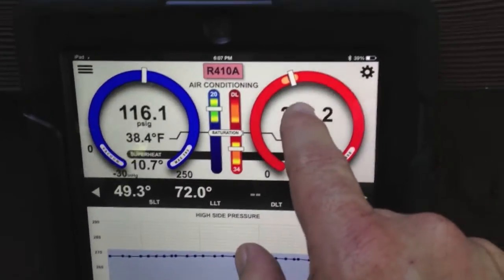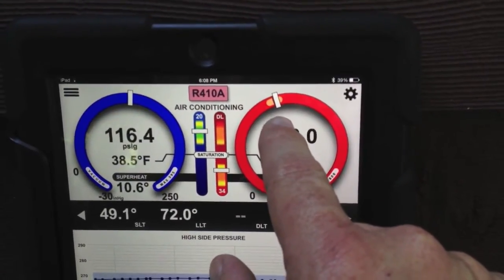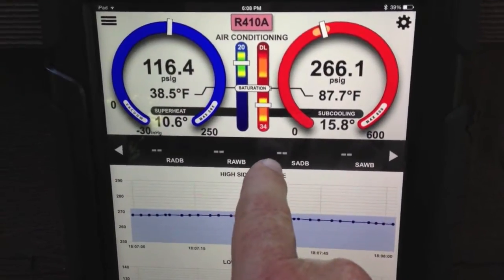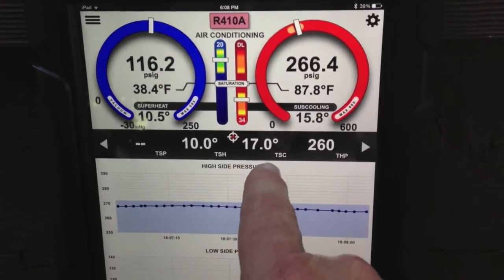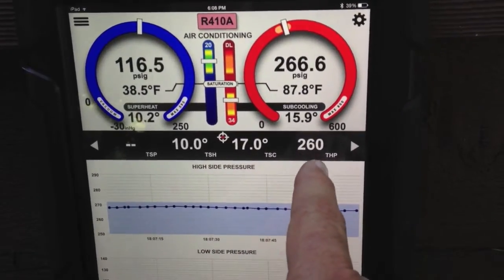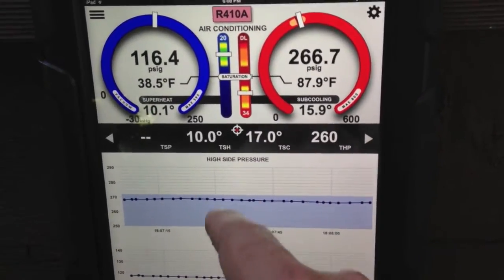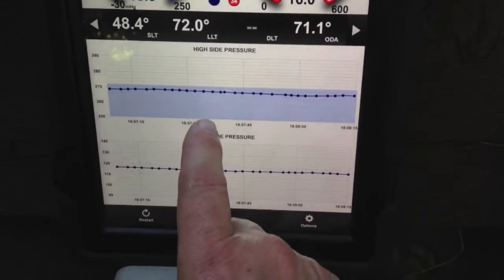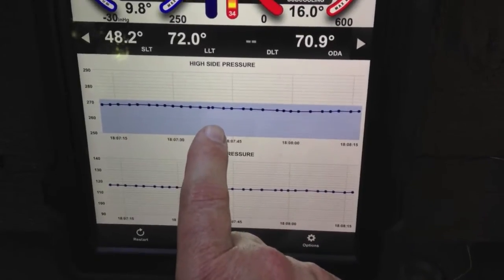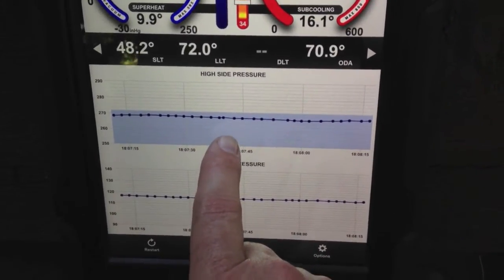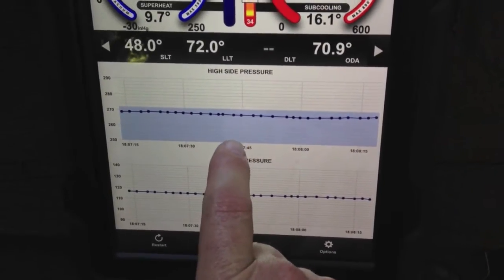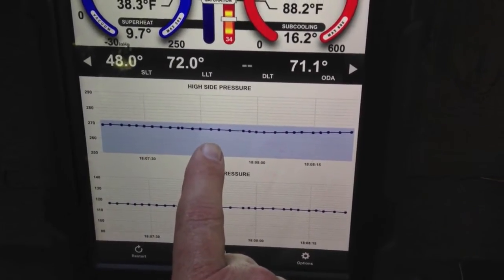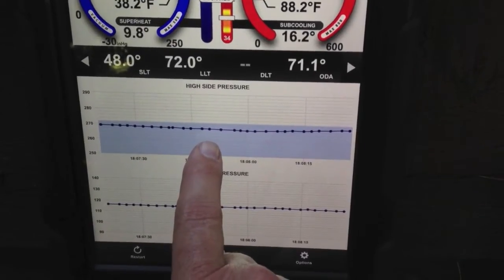Now we get an outdoor target. We don't have an indoor target yet because I haven't entered return air wet bulb or dry bulb conditions. I've got a target superheat, a target subcooling, and a target high pressure — which is driven off the outdoor air temperature, so it changes as that changes. When I put in the targets, I now have this band representing plus or minus three degrees of saturation. As long as I'm inside the band, my high pressure is right on the money.